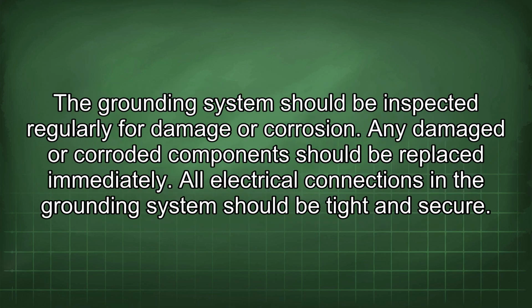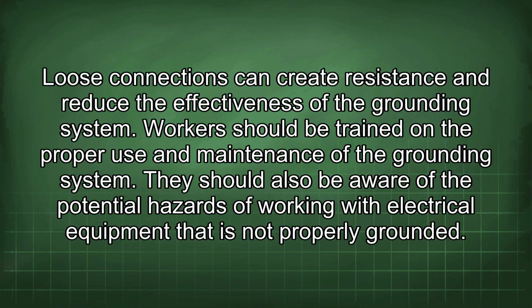The grounding system should be inspected regularly for damage or corrosion. Any damaged or corroded components should be replaced immediately. All electrical connections in the grounding system should be tight and secure. Loose connections can create resistance and reduce the effectiveness of the grounding system.